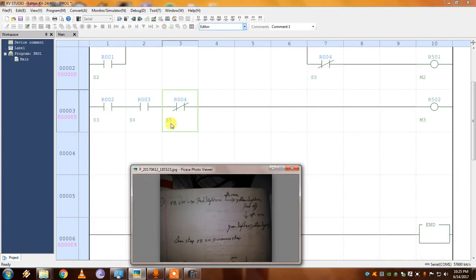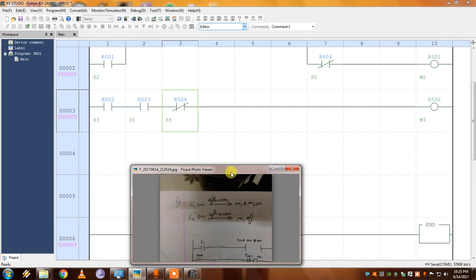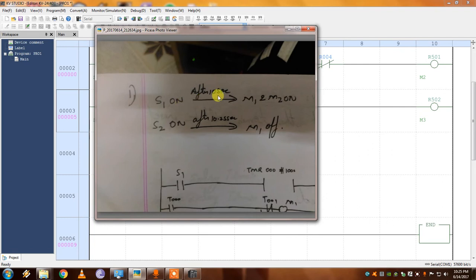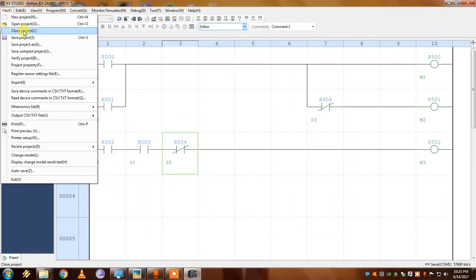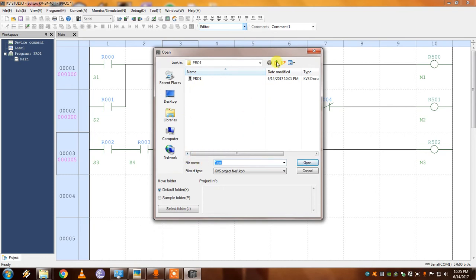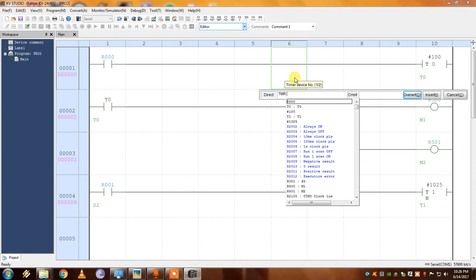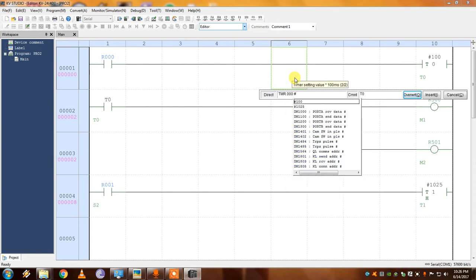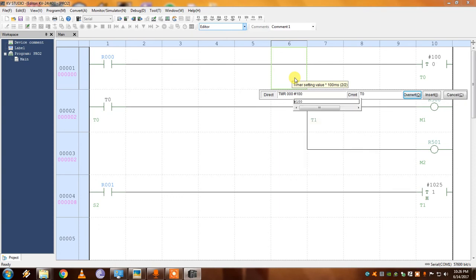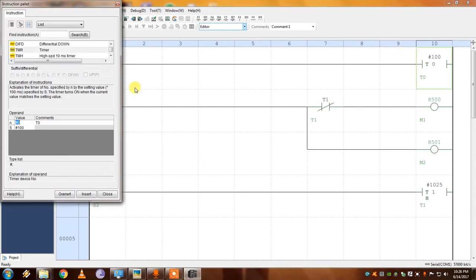Let's go to the second problem — a timer problem. If S1 is on, after 10 seconds, M1 and M2 turn on. If S2 is on, after 10.25 seconds, M1 turns off. I've already done this program, so let's open it — Pro 2. To insert a timer, click on the rung and type the syntax: TMR space address 000 space, then for 10 seconds divided by 0.1, the value is 100. You can also add a comment or name to the timer block.